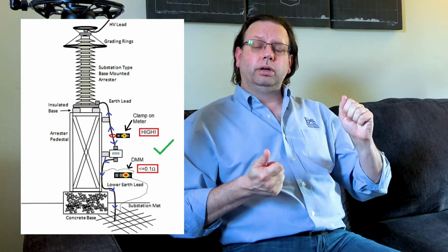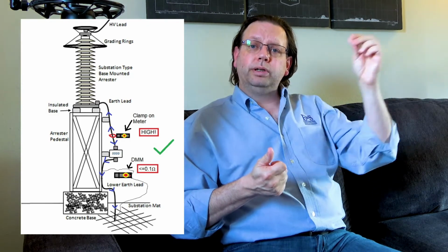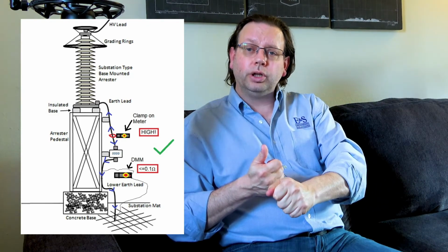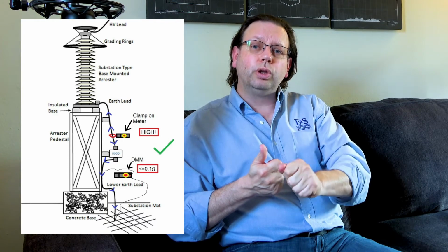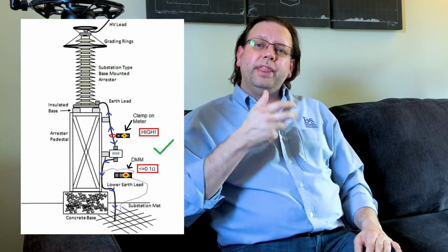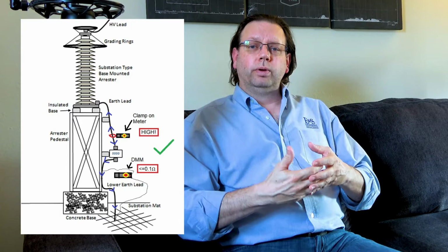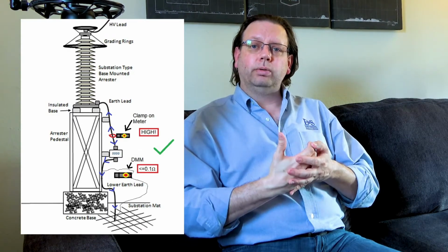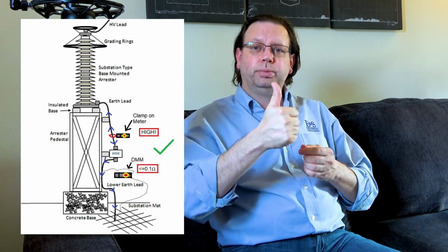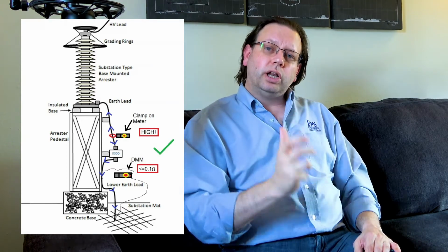Our 2-point meter, meanwhile, if we brought it over and we tied to it, it would show it as a low, a closed, right? It's going to show a low resistance. So that is actually what we're looking for. That's called an isolated ground, right? It has a single connection point to it. And by using our clamp-on meter, which shows a high resistance, and our 2-point meter at the same time showing a low resistance, we can confirm that that is in fact a properly bonded system that is an isolated ground.